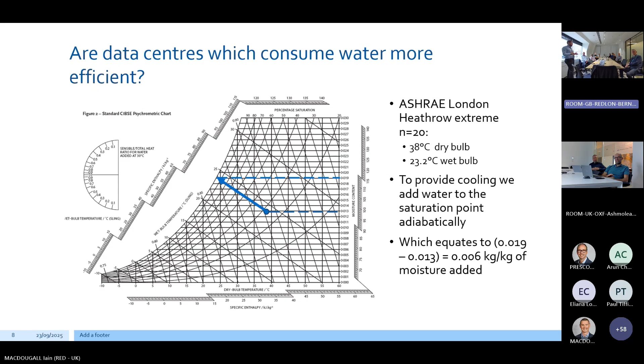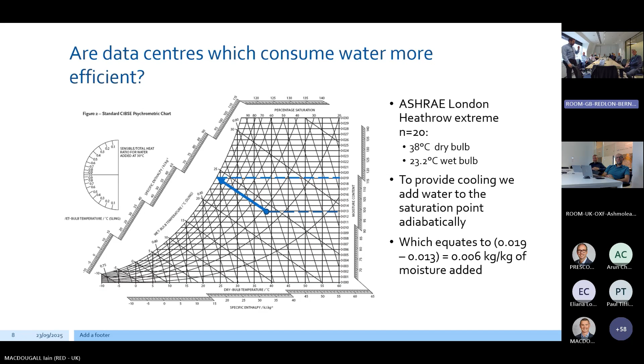To provide cooling, we add water up to the saturation point. I'm just doing this for simplicity, adiabatically. There are other ways of doing it, but let's just concentrate on adiabatically for the moment, which equates to 6 grams of moisture of water added per kilogram of dry air. Fairly simple for psychrometric calculation. However, when we do that, that actually provides 14 degrees C of cooling.